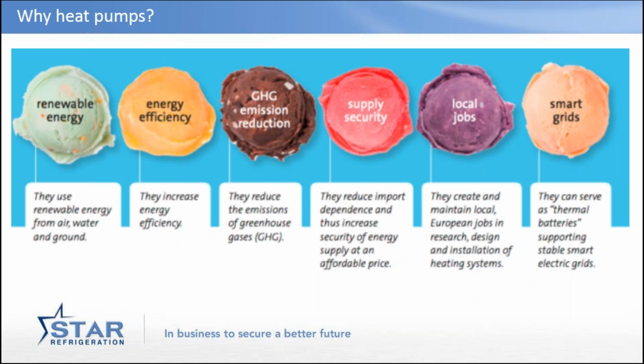So what we see with heat pumps is, A, about how to use them best, but it's about what flavour of ice cream you want. And frankly, we should want them all, whether it's on the right hand, where smart grids are essentially about running heat pumps dynamically to help influence the performance of the grid, by buying more electricity when there's more electricity in the grid and buying less, unloading, essentially turning the heat network into a thermal battery. That is really critical in how we work this. The price of electricity varies from negative at certain times of the day and year in the UK to way higher than what you would consider to be rational, up to 75 pence per kilowatt hour.